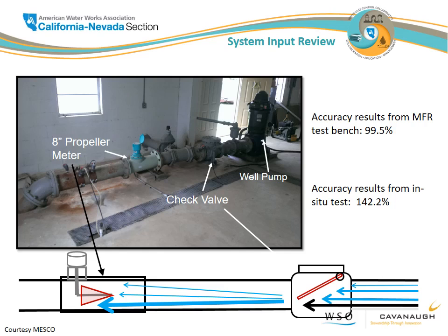Other interesting examples from our friends at M.E. Simpson, where the placement of the meter relative to the check valve in the middle of that run of pipe was creating a situation where the water column and the speed of the water at the bottom of that column was faster and caused the turbine mechanism to overspeed on the meter.